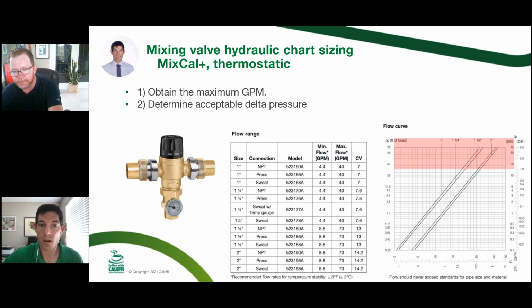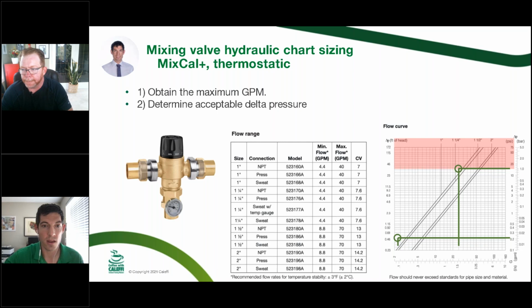Sure. So let's say we want to try a thermostatic valve just as a first pass at this. Mixing valves are going to have these flow curves in the technical data. This is the best way, on the bottom right there, to actually see what the different flows look like for the CV of the valve, because it is a curve like that. You can look at the chart in the middle there and get a general idea that, okay, 1 inch: minimum of 4.4 GPM, maximum of 40.